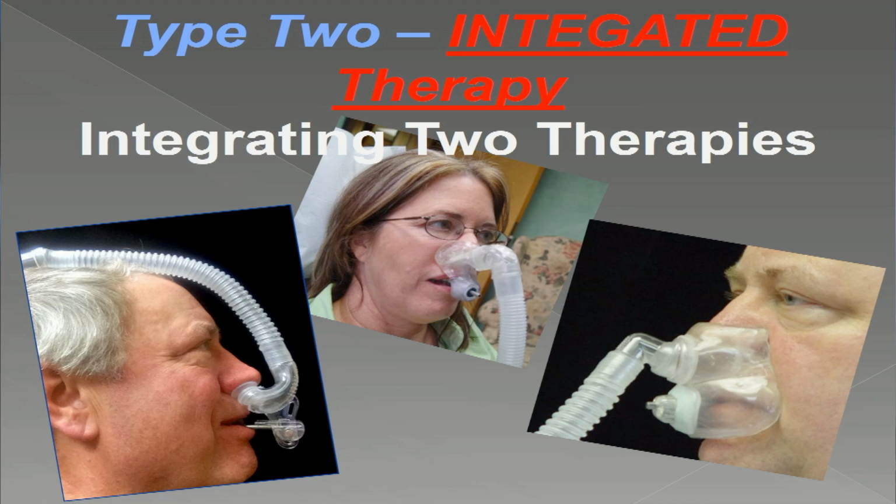And now I'm looking at this. Look at the nose. All right. See where the bridge of the nose is? That's a very big area of complaint for patients with the CPAP mask, especially the full ones, because that skin up there is very thin. And they come in with sores on the bridge of the nose. And I had a patient come in who developed cancer because of the constant irritation. And so this mask is designed not to support itself on the bone of the nose, on the bridge there, but rather to grip the soft end of the nose to make the perfect seal.